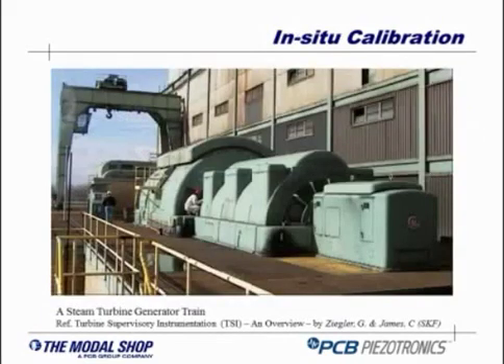But what I want to emphasize today is that most of the time we sell this product, we're doing the opposite: we are taking the calibrator to the sensor site. That's the concept we call in situ calibration, where you have customers, primarily industrial customers, with big machines like the steam turbine you see in the picture. Those machines are instrumented with several different sensors, many of them vibration monitoring sensors, and there's a need to verify if those sensors are actually working properly.